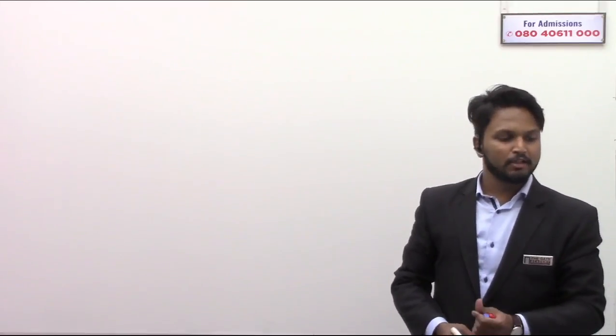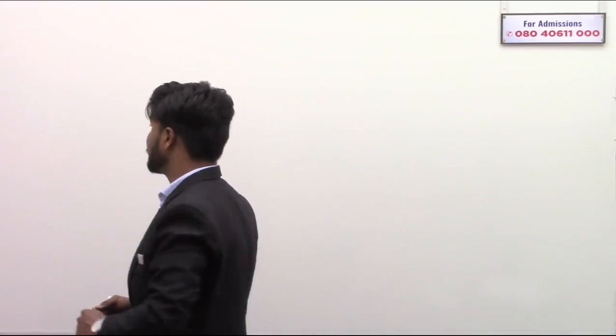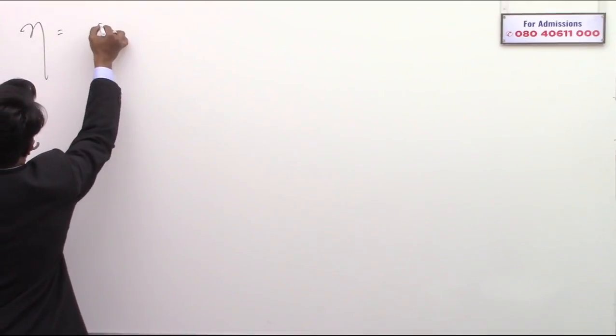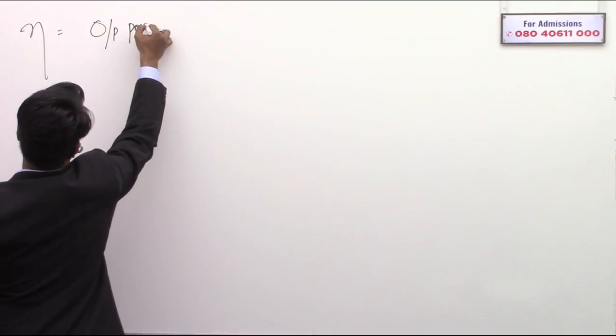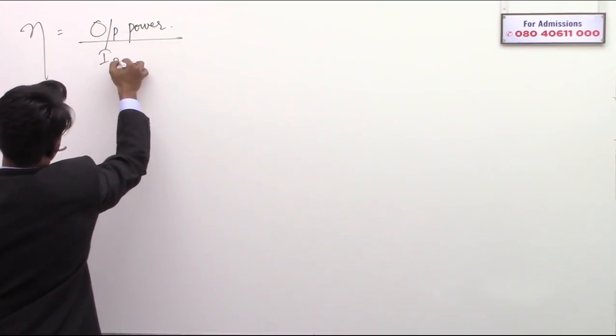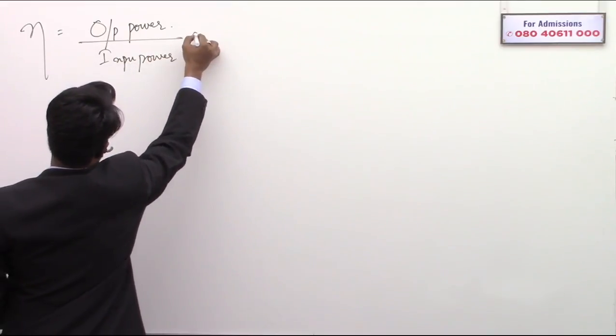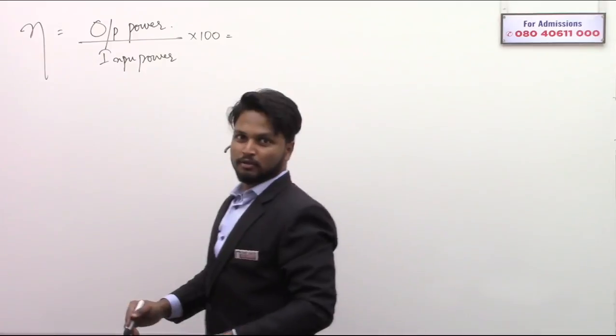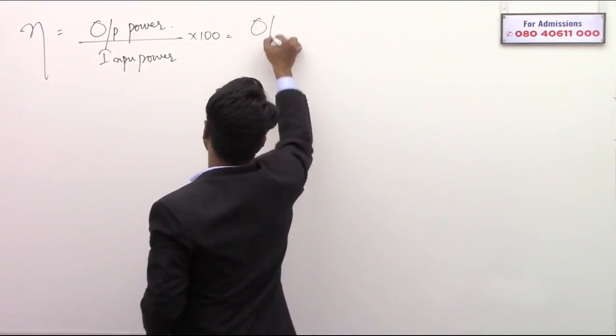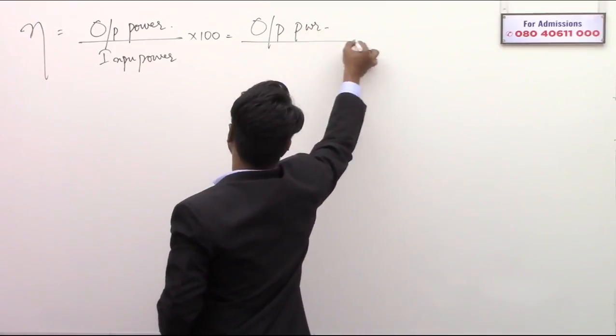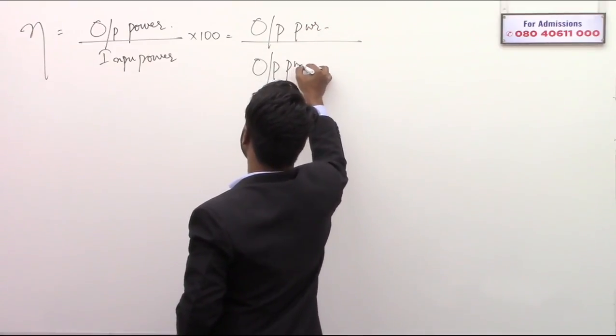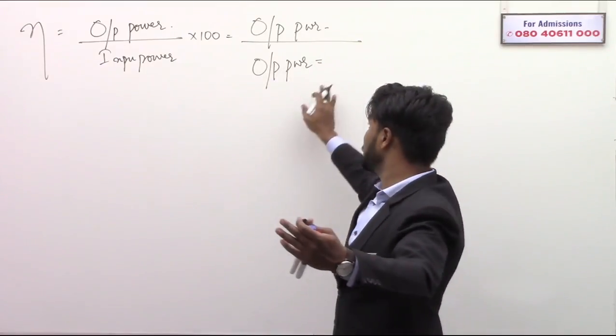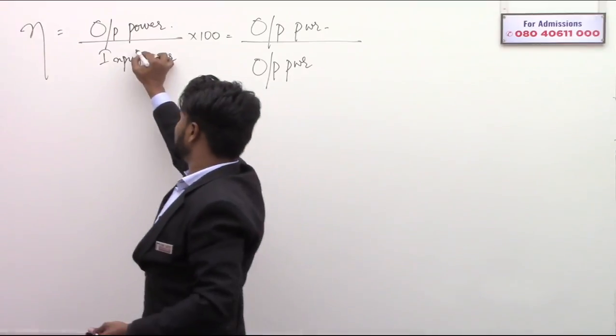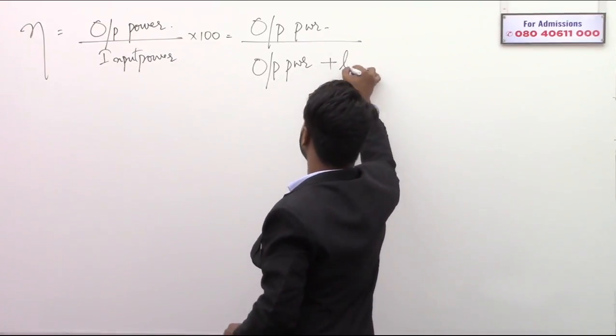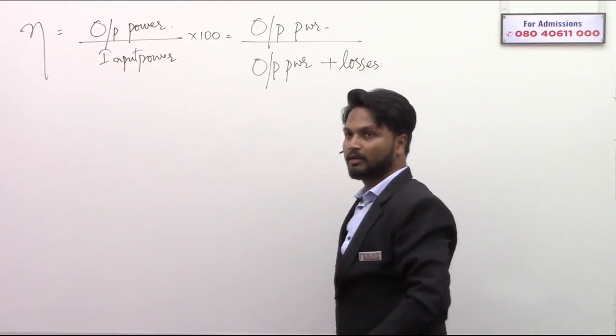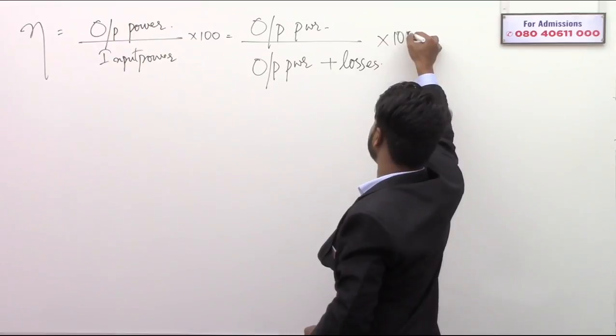So see, the efficiency at 0.8 power factor lag, this you have to find out. Efficiency is generally output power by input power multiplied by 100. So you can write this in this manner: output power by output power plus losses. Input power minus losses is equal to output power. Therefore, input power you can write as output power plus losses. So this multiplied by 100 gives you percentage efficiency.